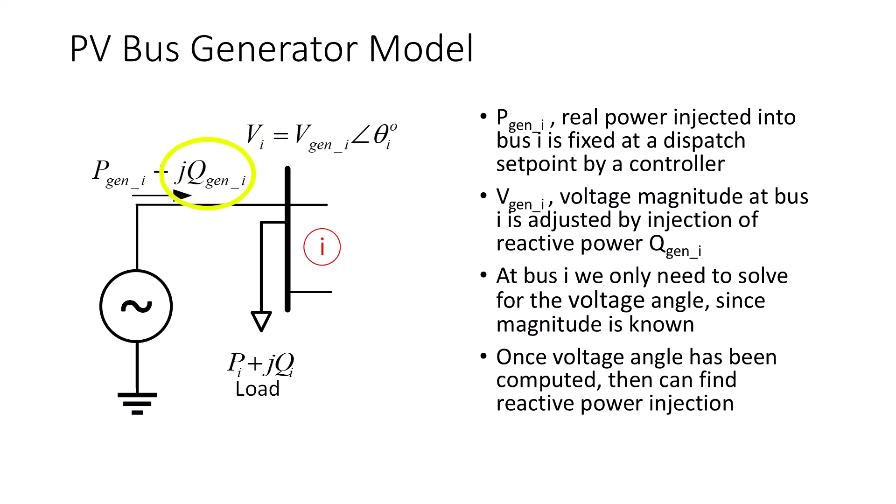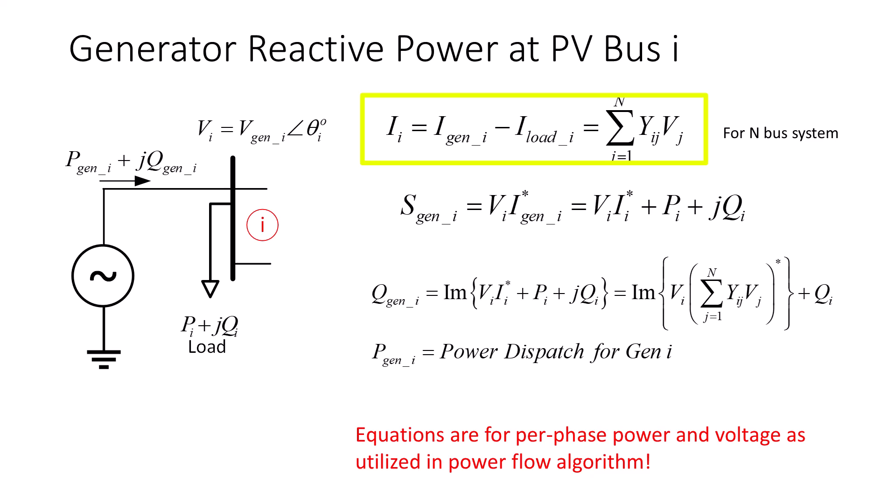The net injected bus current, I sub I, that we find by multiplying the i-th row of Y bus by the voltage matrix is equal to the difference between injected generation current and load current as shown here. The injected generator complex power is VI times the conjugate of the injected generator current, which is equal to V times the conjugate of current plus the load power. We can use this relationship to find the reactive power, QGen, by taking the imaginary part of the complex generator power. Note these equations are for single-phase power, so as to be consistent with the per-phase model utilized in the power flow program.